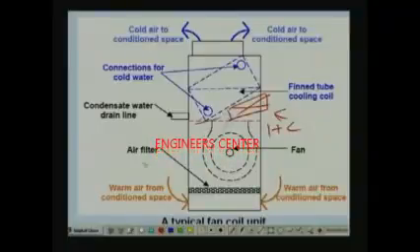In addition to a cooling coil, you can also have a heating coil — in a 2-pipe system this would be an electrical heater, while in a 4-pipe system it is a hot water coil. The capacity of the fan coil unit is controlled either by controlling the water flow rate, the supply air flow rate, or both, with supply air flow rate controlled by varying the fan speed. In a typical fan coil unit, separate arrangement must be made for ventilation, since there is no built-in provision for supplying outdoor air.